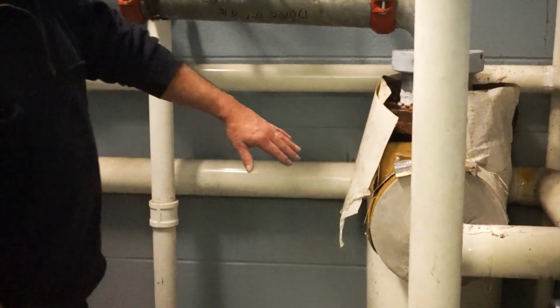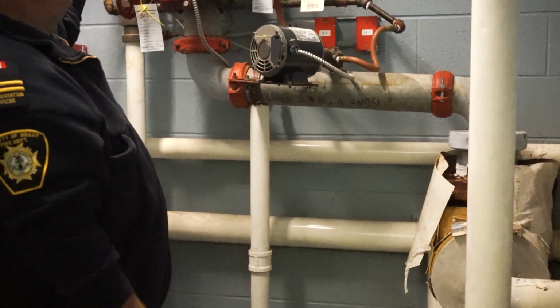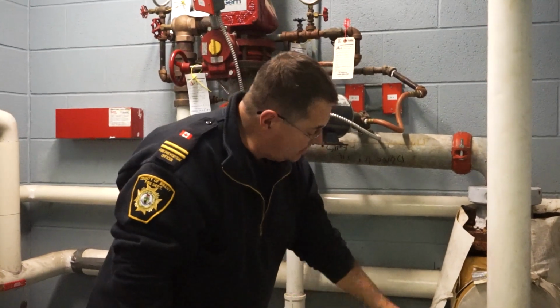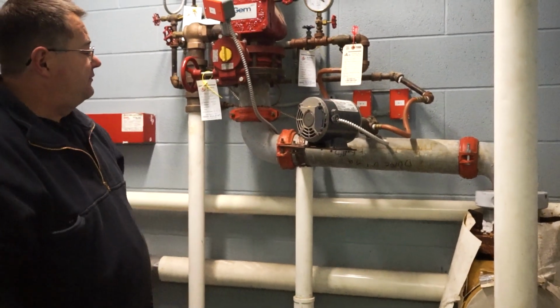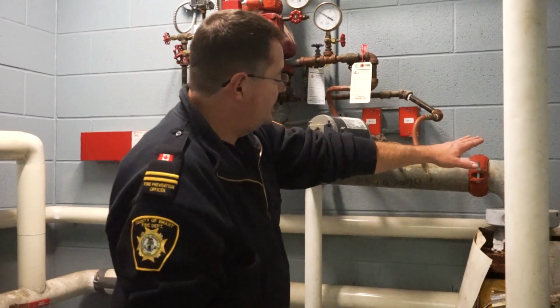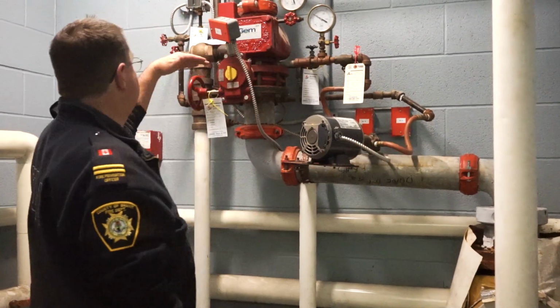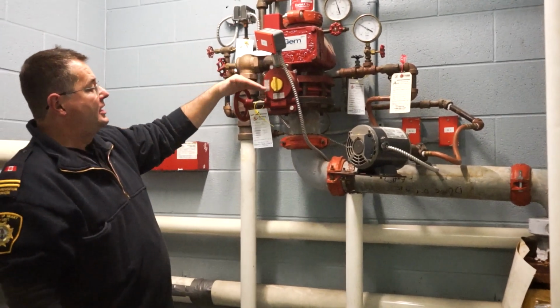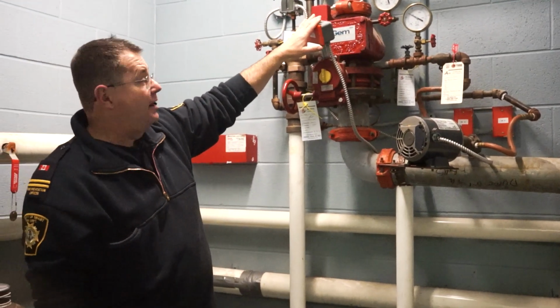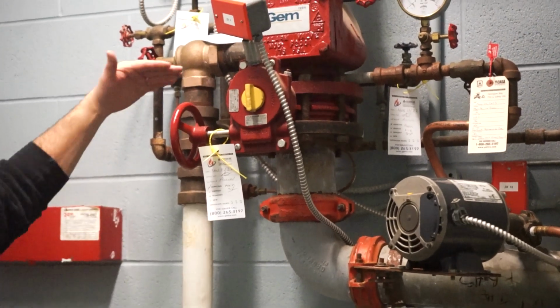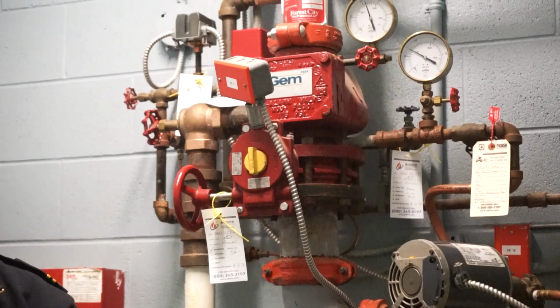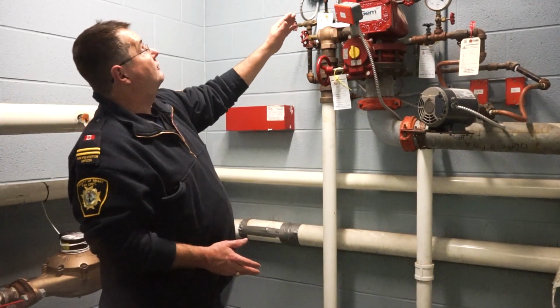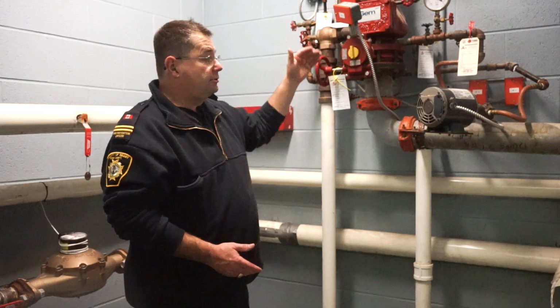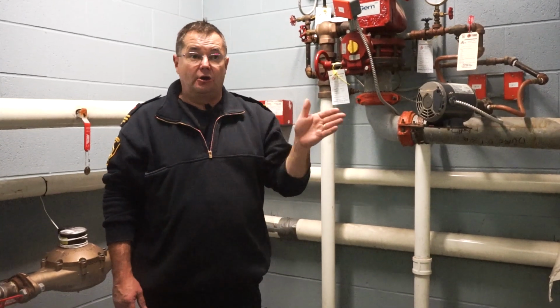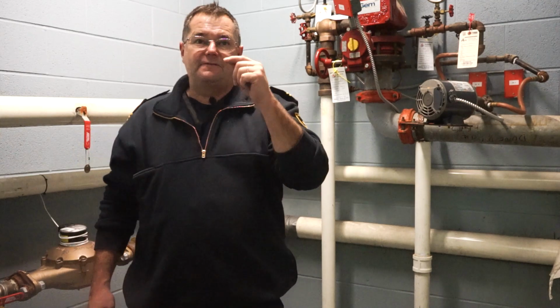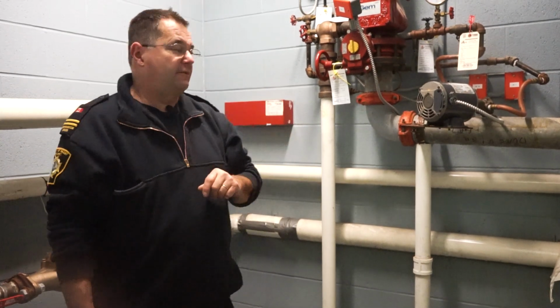Their job is to add water to the system and help the water that's coming in from the water main put out the fire. The water comes up from the ground up to the system, and as soon as we reach this point, this is a valve that is monitored by the fire alarm, and this lets us know when the valve's opened or closed at the fire alarm. All the system knows is we've got water flowing. That means we have a fire. So when the sprinkler system activates, it lets the fire alarm know. The fire alarm goes off, and the fire alarm calls the fire department for help to come here and see if there's a problem.